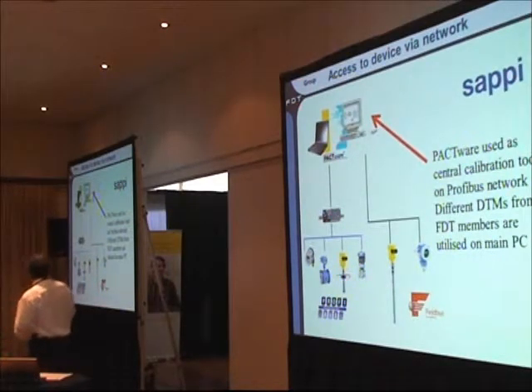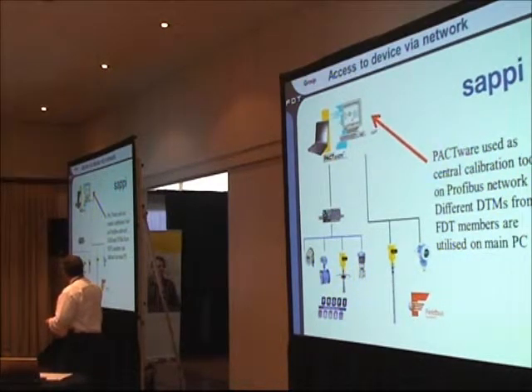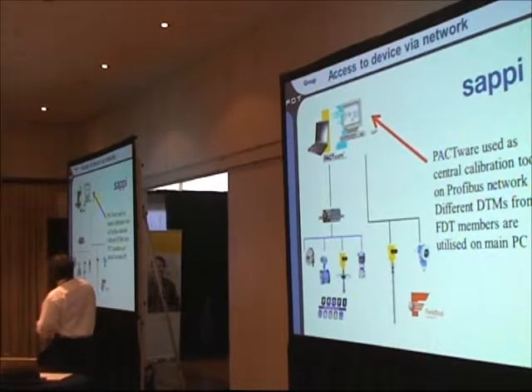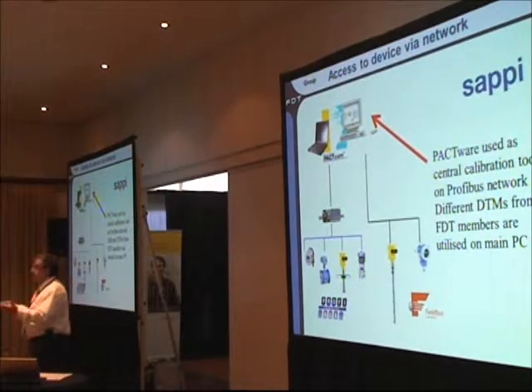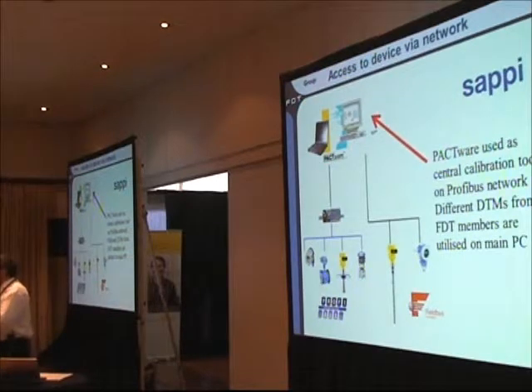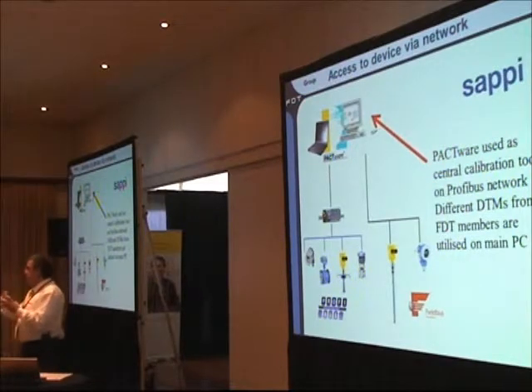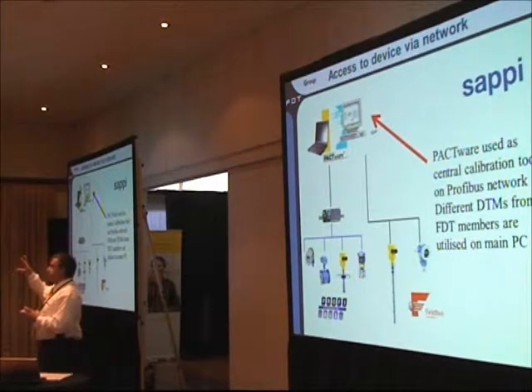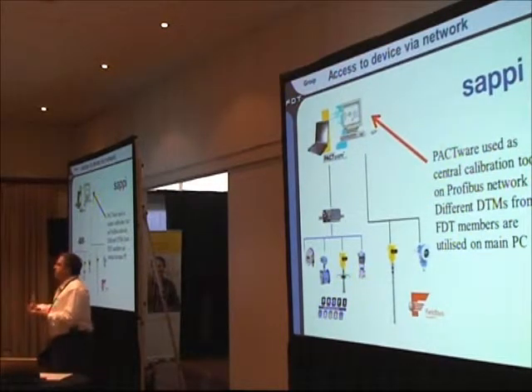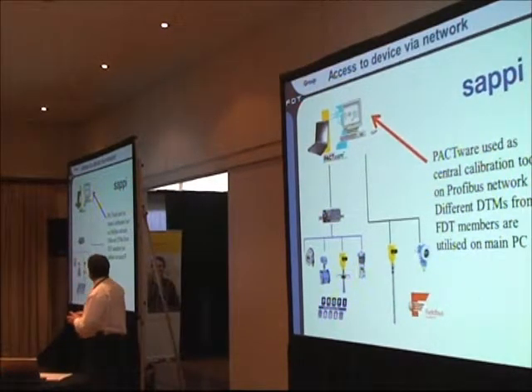Therefore, it's sometimes interesting to use a complete fieldbus, and this is exactly what this system does. They use Profibus with a Profibus master above. PACTware is used as Profibus master, master class 2. The DCS system is master class 1, the real working DCS, and PACTware as a separate master class 2 does the configuration job and maybe also some kinds of diagnostics if necessary.